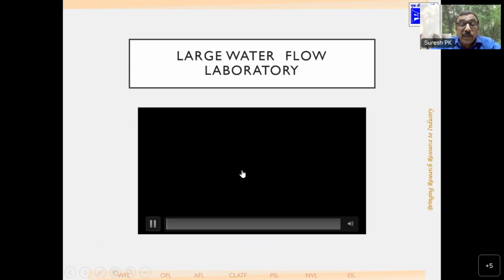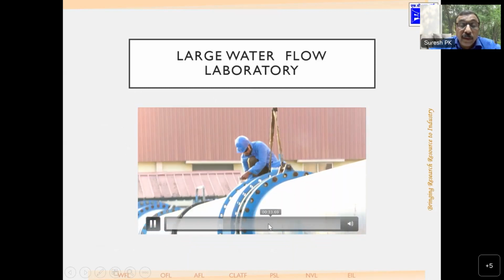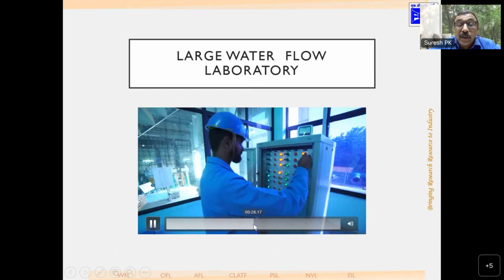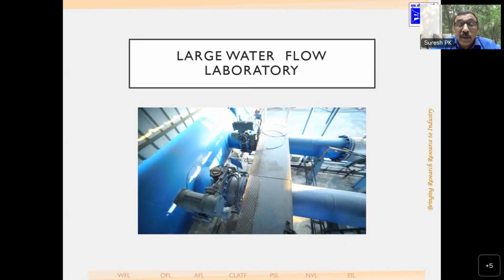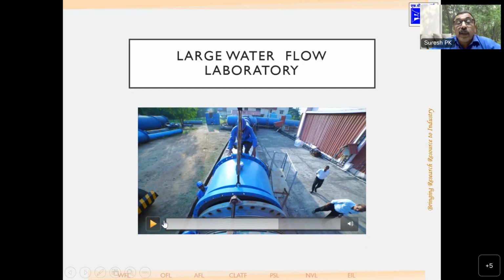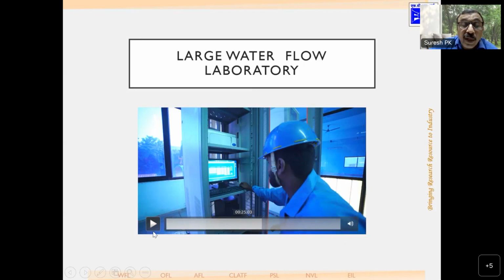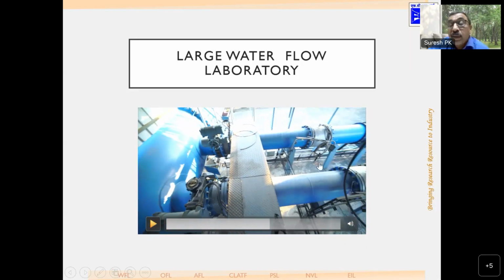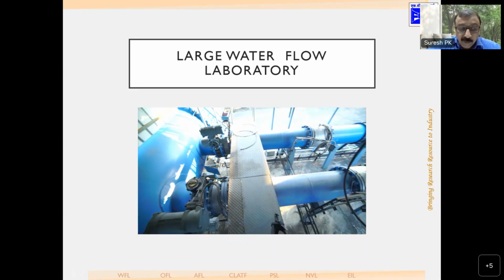In this system, you can see that the master meter is utilized for the measurement of the system. These are the master meters which are used for measurement, and these meters are calibrated against the gravimetric system in the water flow laboratory. But of course, the uncertainty is of the order of 0.5% in this case, not 0.2 or 0.1%, as has been the case in the water flow laboratory.